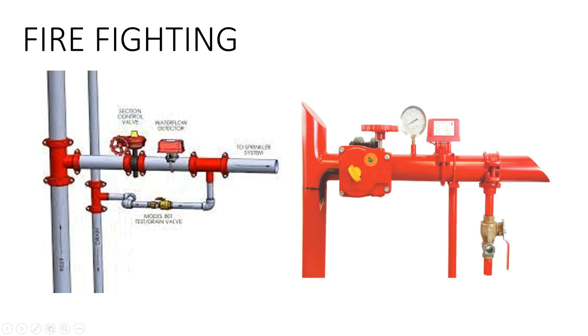Then you have the tee, a mechanical tee. On the downside you can find the drain valve for inspection and testing purposes. As you can see, it's a test and drain valve. It has a transparent type window, so as you can see in this picture, you can simply see whether the water is flowing through these pipes or not when you open the valve. So this is the advantage of this valve. It is mostly useful for testing purposes, when you do the testing and commissioning, or when you change the water, you will be using this.